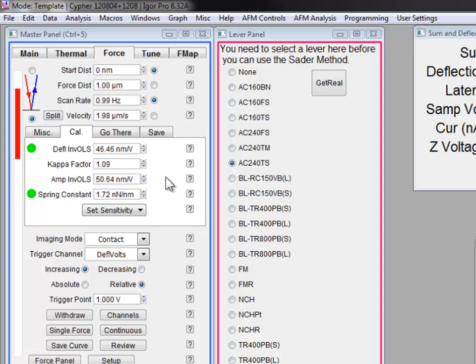So now that I have both my sensitivity and my spring constant, I can start making some quantitative measurements with this cantilever. Using the sensitivity, I can convert my amplitude or my deflection into the real cantilever movement in nanometers. I can also convert my force curves into newtons for quantitative force measurements.